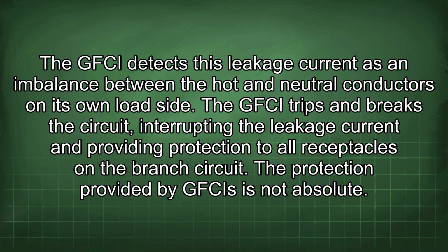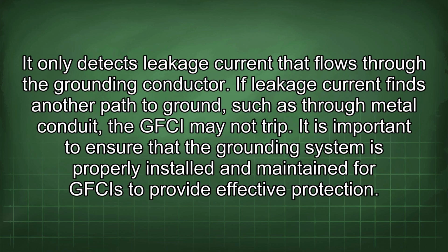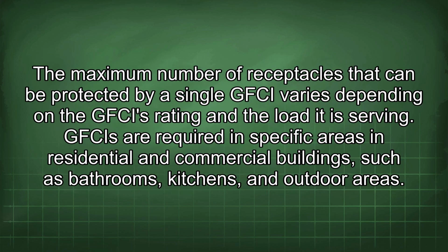The protection provided by GFCIs is not absolute. It only detects leakage current that flows through the grounding conductor. If leakage current finds another path to ground, such as through metal conduit, the GFCI may not trip. It is important to ensure that the grounding system is properly installed and maintained for GFCIs to provide effective protection. The maximum number of receptacles that can be protected by a single GFCI varies depending on the GFCI's rating and the load it is serving. GFCIs are required in specific areas in residential and commercial buildings such as bathrooms, kitchens, and outdoor areas.